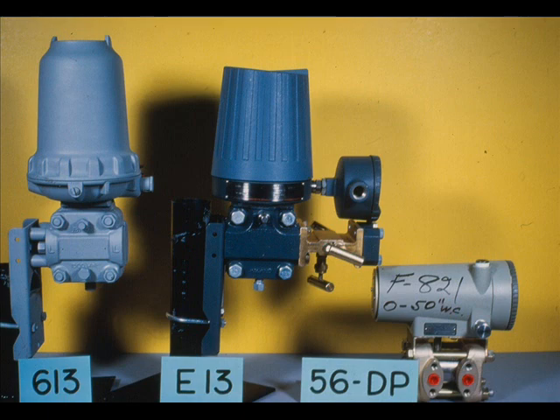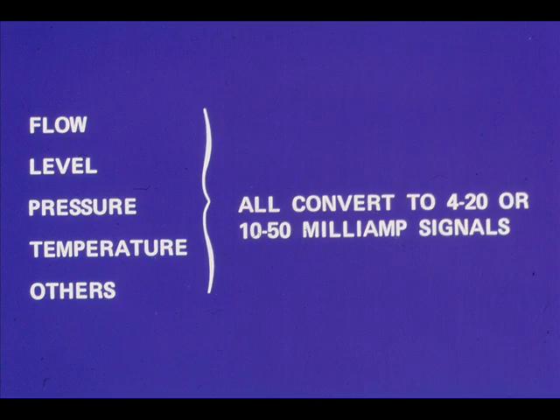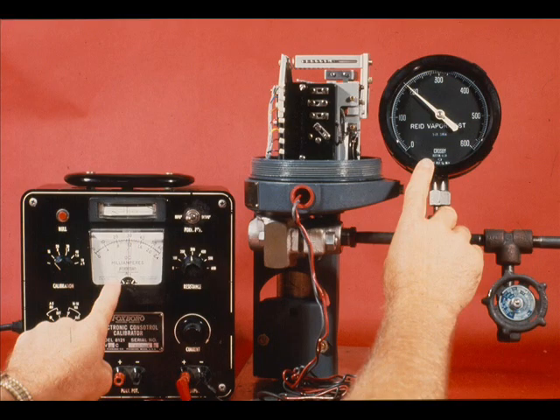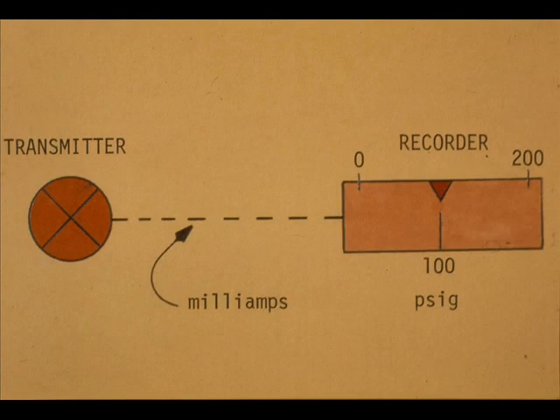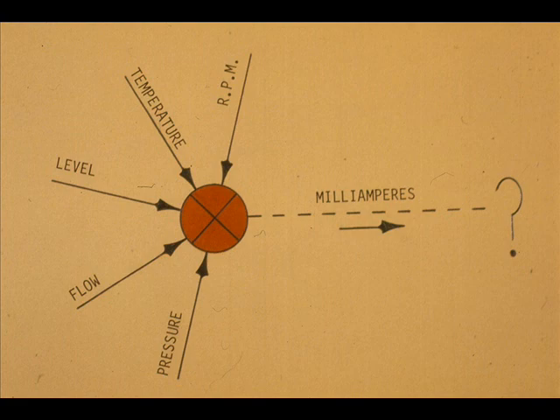Electronic transmitters use either a 4 to 20 or 10 to 50 milliampere output signal. The transmitter may measure flow, level, pressure, temperature, or other variables, but the transmitted signal is in milliamperes. For calibration purposes, we must convert these process input signals to the correct milliamp output signal. Our objective is to determine the correct milliamp output for a given process input.